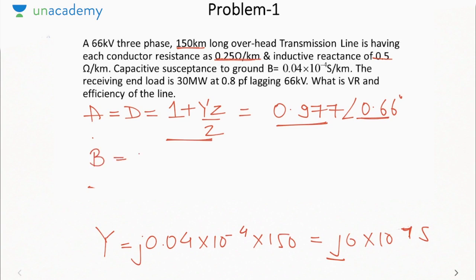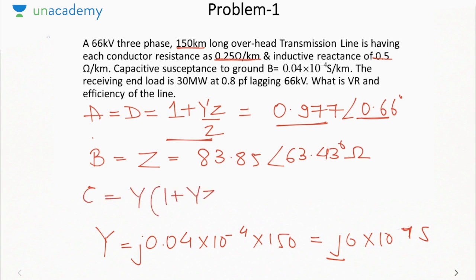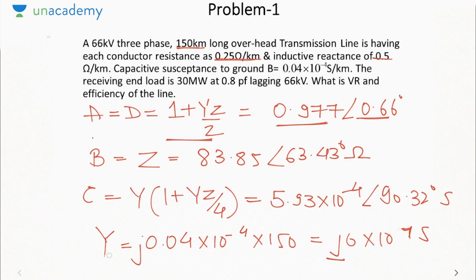For the pi model, B is equal to Z, 83.85 angle 63.43 degree ohm, and C will be equal to Y into 1 plus YZ by 4. I am not substituting the values here, but if you substitute, you will get these parameters. It will be 5.93 into 10 raised to the power minus 4 angle 90.32 degree Siemens. So these are the parameters of the nominal pi model.